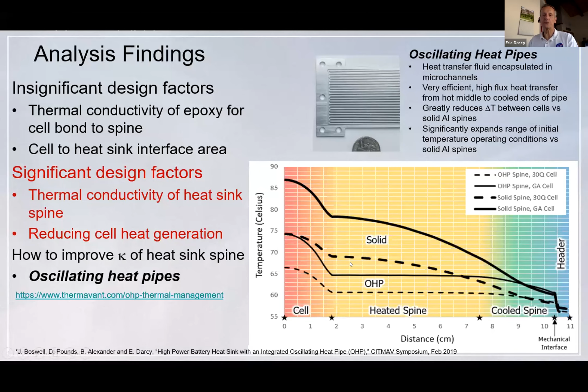That told us we would never get there with solid aluminum at the higher 20-minute discharge rate. We needed something much more conductive: the oscillating heat pipe, with micro channels loaded with ammonia, from a company that has the IP for this, Thermavant Technologies — I encourage you to check out their website and learn more about their technology. It greatly reduces the thermal gradients between the cells.